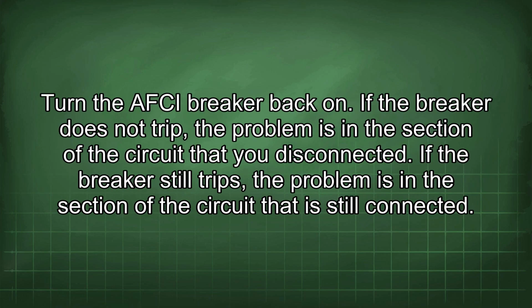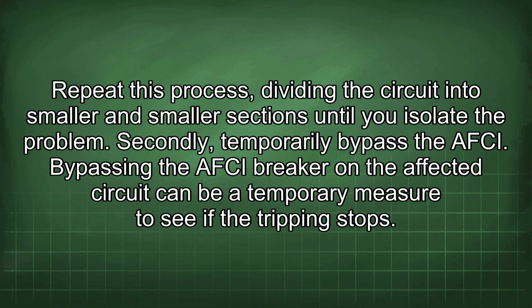Turn the AFCI breaker back on. If the breaker does not trip, the problem is in the section of the circuit that you disconnected. If the breaker still trips, the problem is in the section of the circuit that is still connected. Repeat this process, dividing the circuit into smaller and smaller sections until you isolate the problem. Secondly, temporarily bypass the AFCI.